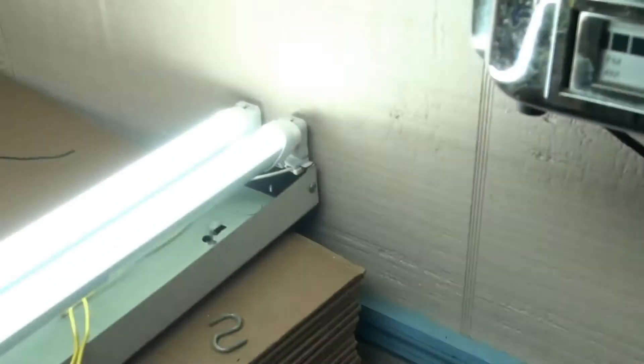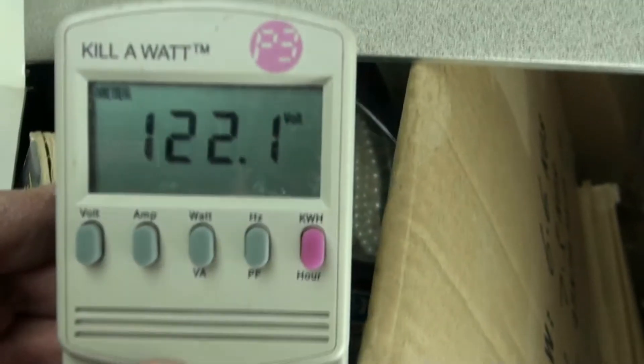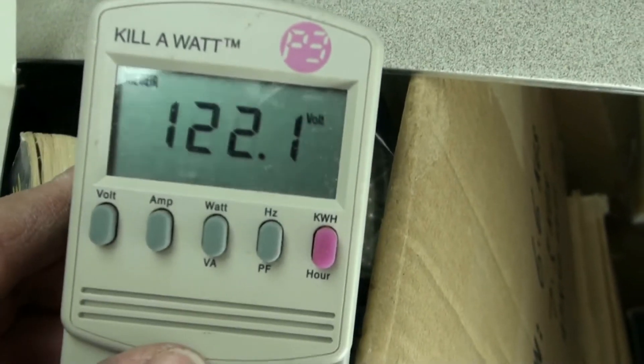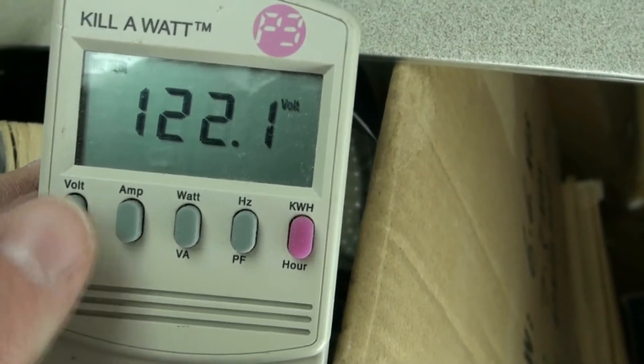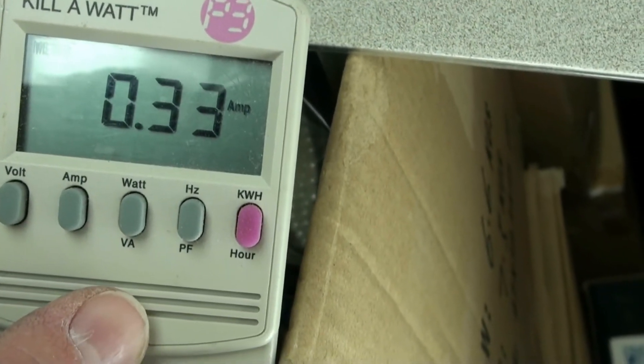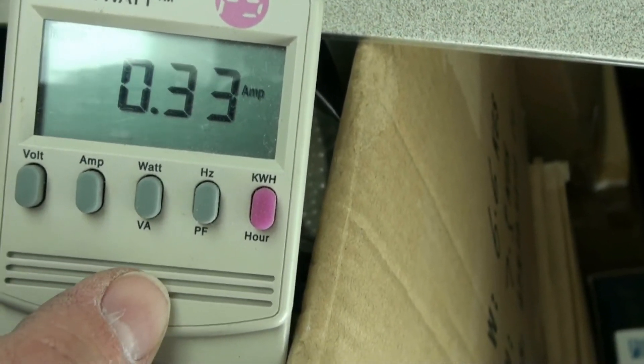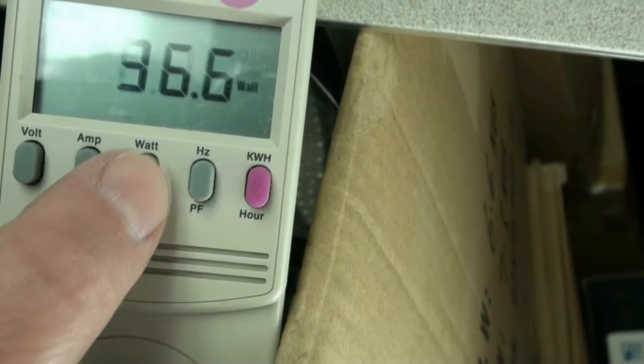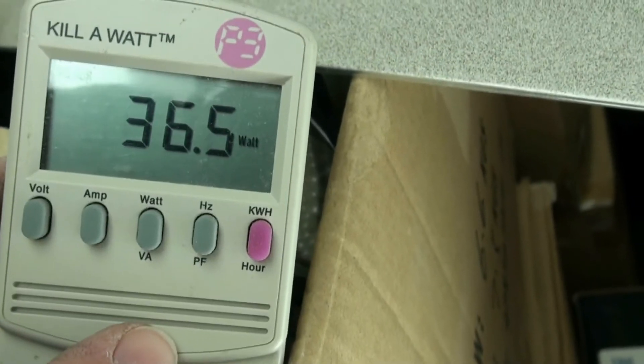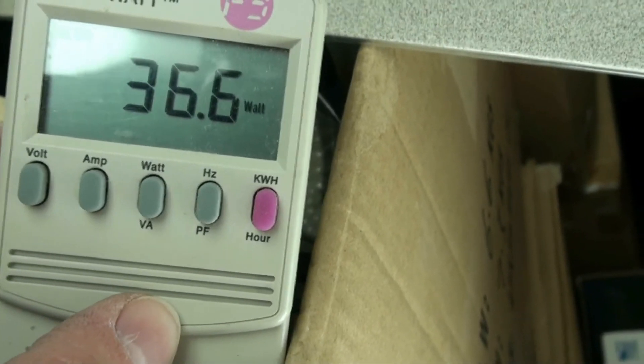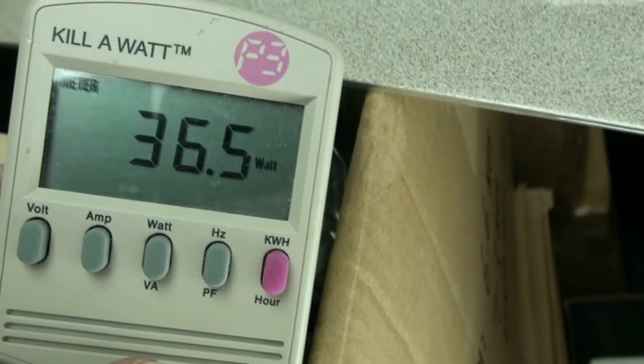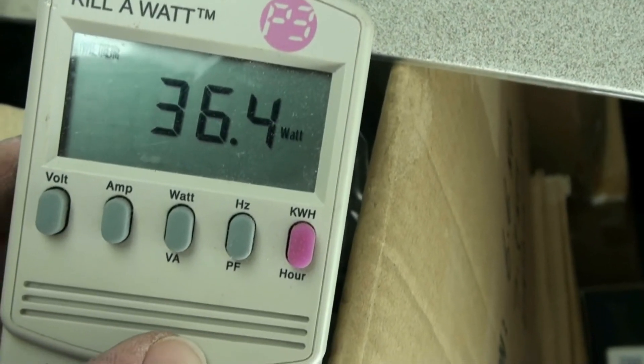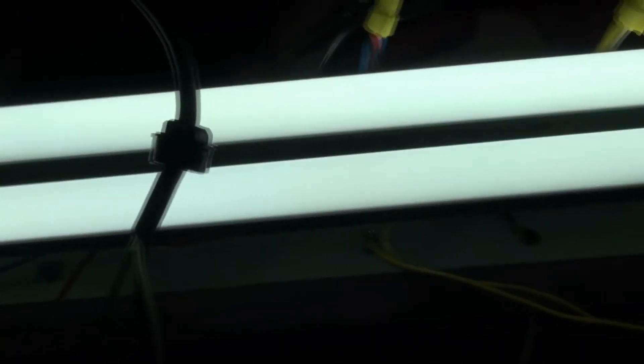All right, let's light it up. Okay everybody, as you can see she's well lit. If we come up and take a look at the Kill A Watt meter, we're still at 122 volts, pulling 0.33 amps, which is roughly half of what it was, and using 36 watts. So it was 71, now it's 36. Using these LEDs, it's much brighter and lasts for 50,000 plus hours.